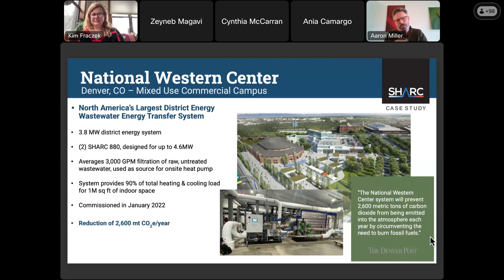This system, and the Lelum project I'm about to show, demonstrates the value of thermal energy networks. In the shoulder seasons the loop self-sustains: you might have a supermarket on one end rejecting 100% of heat into the loop, multifamily residential doing a little heating and cooling, and an aquatic center doing nothing but pulling heat out. By pushing and pulling with this diverse mix of buildings, the loop stays self-tempered, using the SHARC to keep it in the ideal range, 58 to 78 year-round. In winter and summer we ramp up, taking a lot of heat out to the sewer or pushing it in as needed.